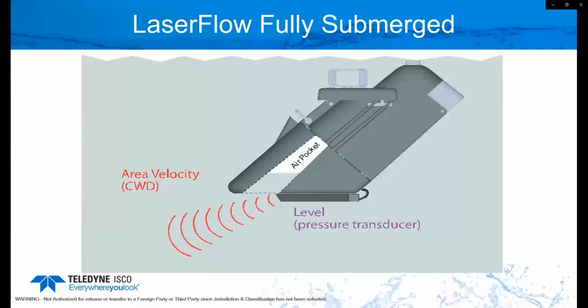So we have another sensor mounted on the bottom. That's going to measure the depth using a pressure sensor, and it's going to use a continuous wave Doppler to transmit out the nose to measure the velocity of the water. The beauty of these is they're typically mounted at the crown of the pipe, so once the water level submerges that sensor, it seamlessly transitions to that other sensor.